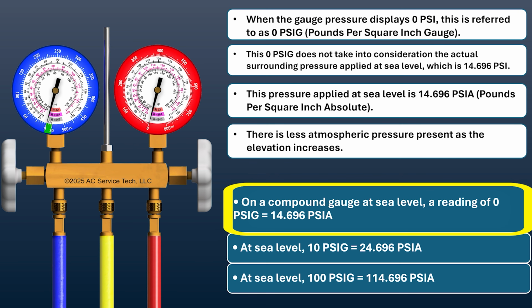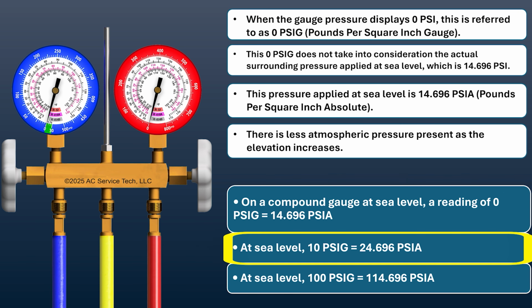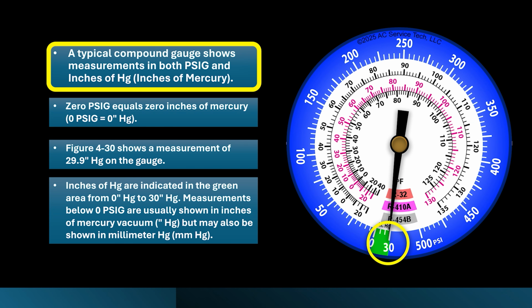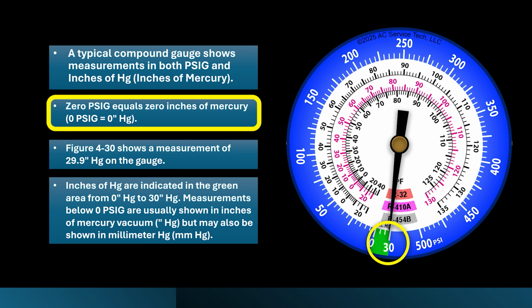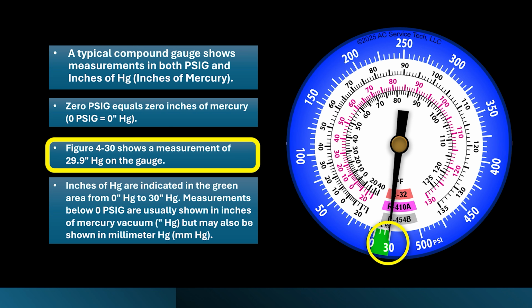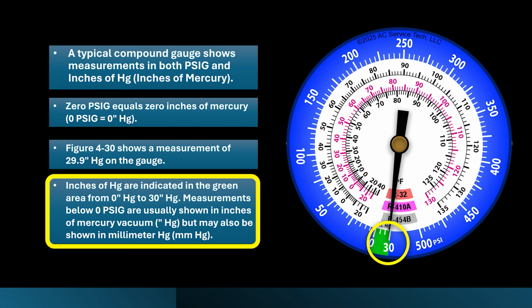On a compound gauge at sea level, a reading of 0 psig equals 14.696 psia. At sea level, 10 psig equals 24.696 psia. At sea level, 100 psig equals 114.696 psia. A typical compound gauge shows measurements in psig and inches Hg. That's inches of mercury. 0 psig equals 0 inch Hg. Figure 4-30 shows a measurement of 29.9 inch Hg on the gauge. Inches of Hg are indicated in the green area from 0 inch Hg to 30 inch Hg. Measurements below 0 psig are usually shown in inches of mercury vacuum, and that means inch Hg, but may also be shown in millimeter Hg, that's mm Hg.